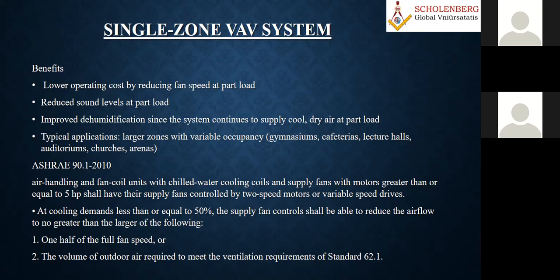So this may be one reason, and you can always take it in there. At any cooling demand less than or equal to 50%, the supply fan control shall be able to reduce the airflow to no greater than the larger of the following: one half of the full fan speed, or the volume of outdoor air required to meet the ventilation requirement of the standards, because ventilation requirements are described in standard 62.1, which we reviewed yesterday.